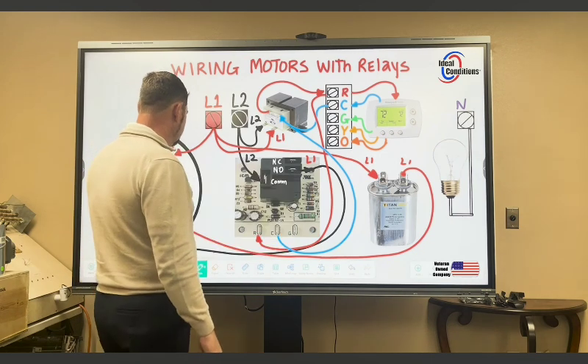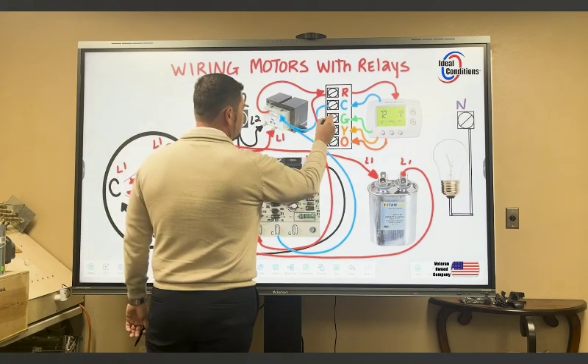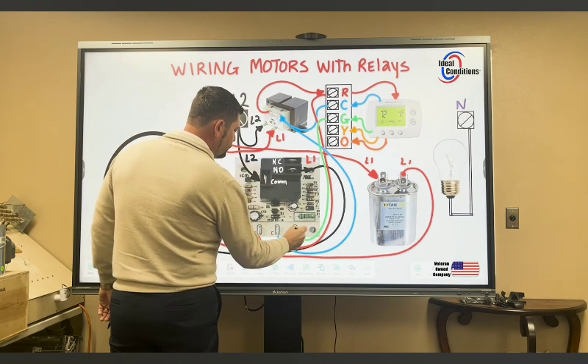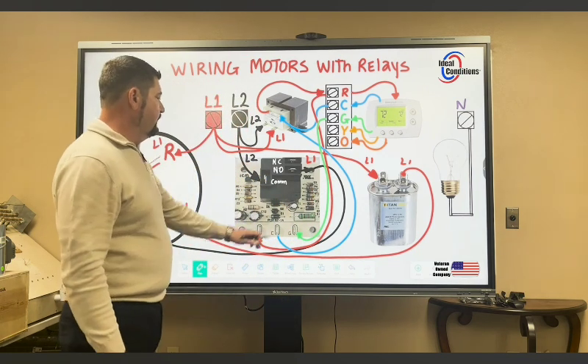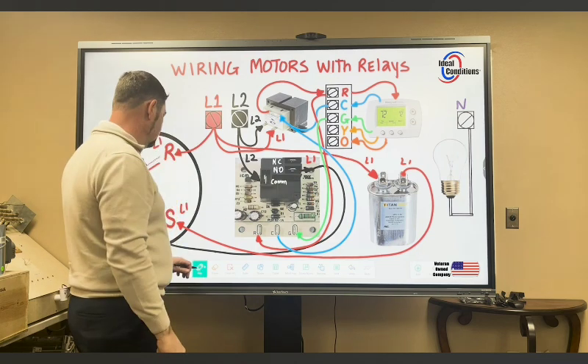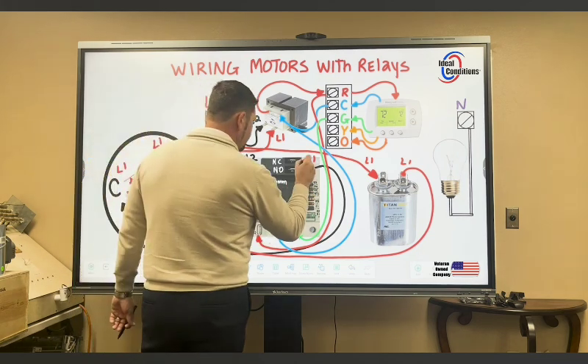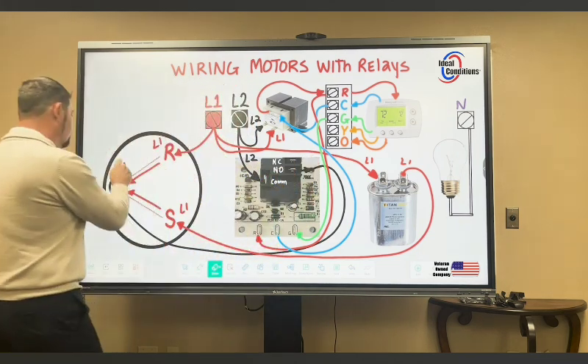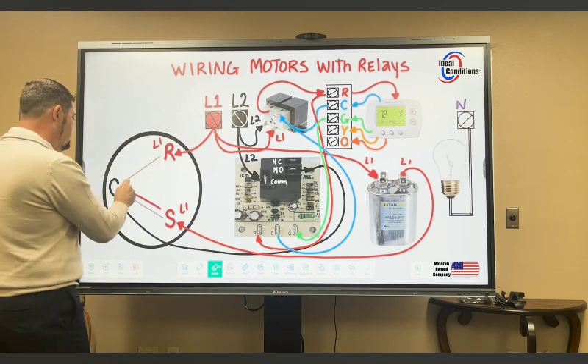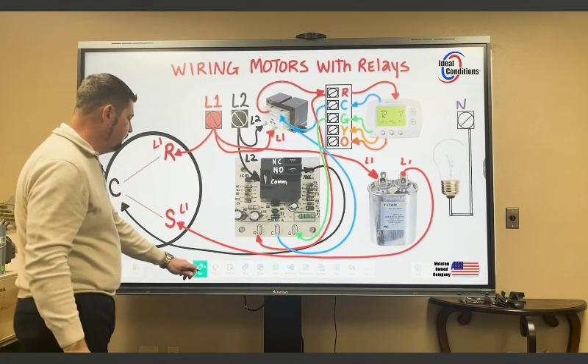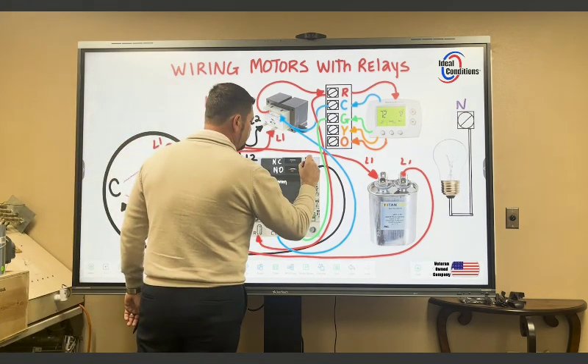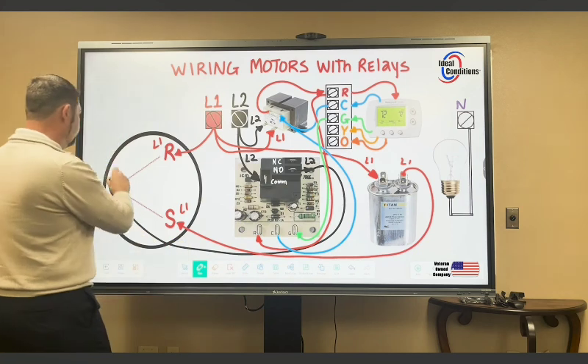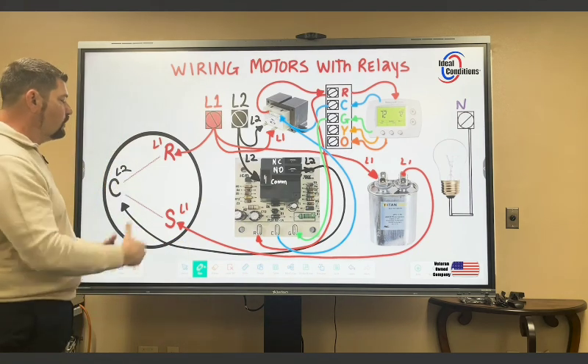Let's go ahead and put the G call up there. The G call off the terminal block over to the blower control board. That now puts L2 here. I'm going to go ahead and erase this L1 value here. We're going to go ahead and take these arrows off because we're about to change the path of electricity. And what we're going to do is we're now going to say that this is L2. And because that's L2, then over here we have L2, and our motor will come on.